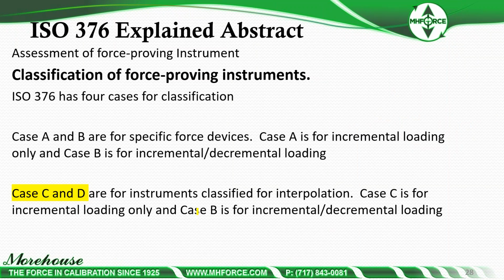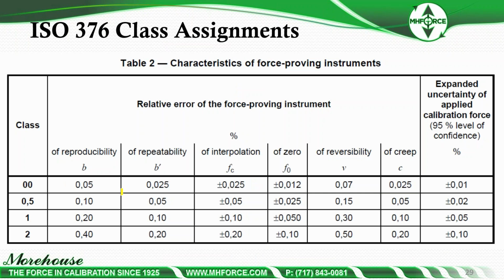And ISO has 4 cases for classification. Case A and B are for specific force devices, which are specific meaning only used at the forces that they were tested at. Case A then is for incremental loading only, and case B is for incremental and decremental loading. Most people are going to be using case C and D, instruments classified for interpolation. Case C is what we see the most of. It's for incremental loading only, and case D is for incremental and decremental loading. So again, case C is you do the creep test, and we see that the most. There's the table again. So we're going to go through all these cases.